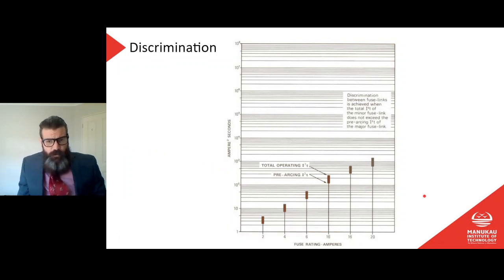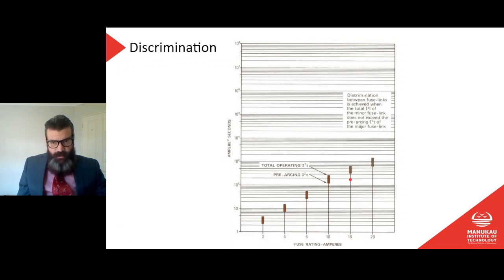If you're struggling with that concept, let me know. And here we have a pretty little graph of total operating I squared T, and pre-arcing I squared T. There's our pre-arcing I squared T there, total operating there. These are different ratings of fuses. You can see these, 10, 16 and 20. So what we're saying is that in order for one to back up the other, the total operating, the top of that brown rectangle, needs to be lower than the pre-arcing, the bottom of the next one, or whichever one we're using as backup.